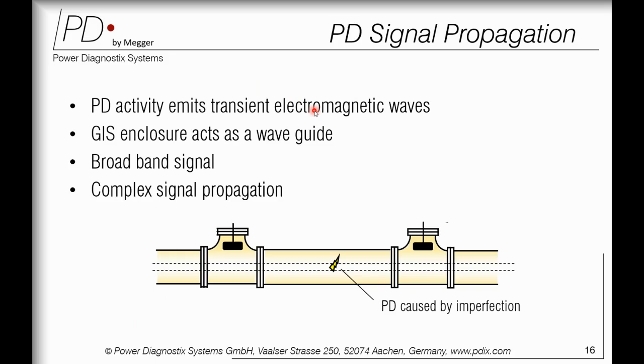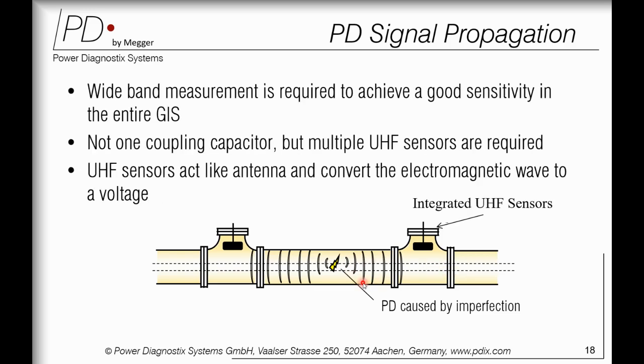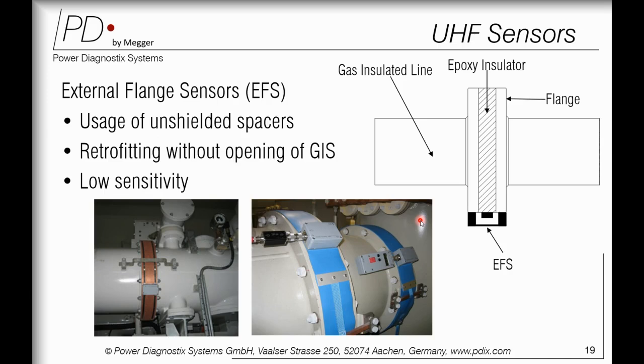When you talk about PD signal propagation, it's quite simple. Let's say this is your GIS enclosure, you have inbuilt UHF sensors, and the PD is caused by some imperfection. This PD will always create electromagnetic waves which will travel back and forth depending on the design of the enclosure, because the GIS enclosure acts as a waveguide, right? Those broadband signals will pass through the complete GIS enclosure. You have an integrated UHF sensor which captures all those electromagnetic waves, and the UHF sensor acts like an antenna and converts those electromagnetic waves to voltage, where you measure the PD in terms of dB microvolt or dBm. So these were some examples when you have inbuilt sensors.